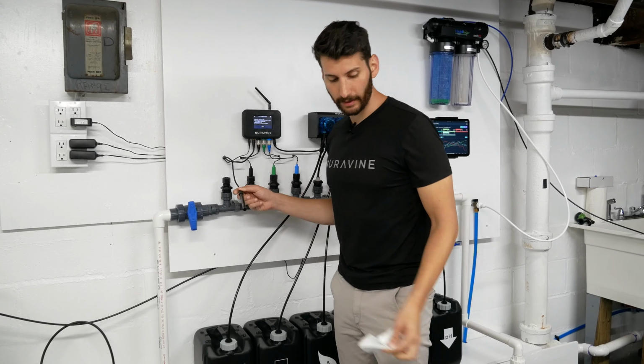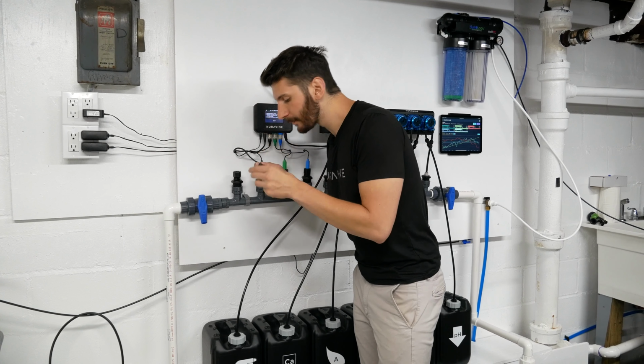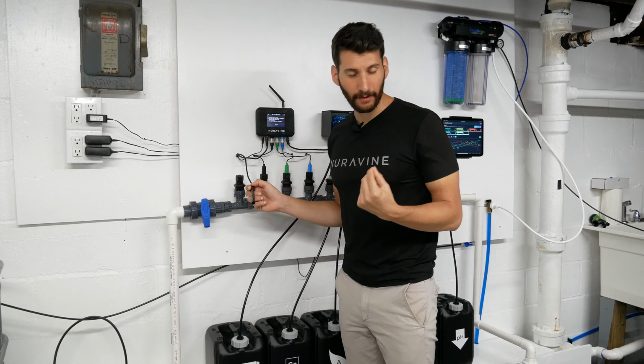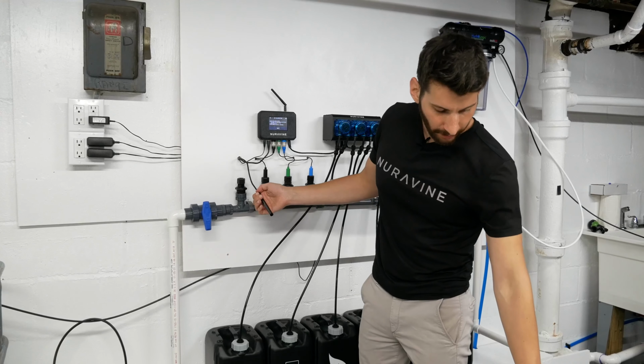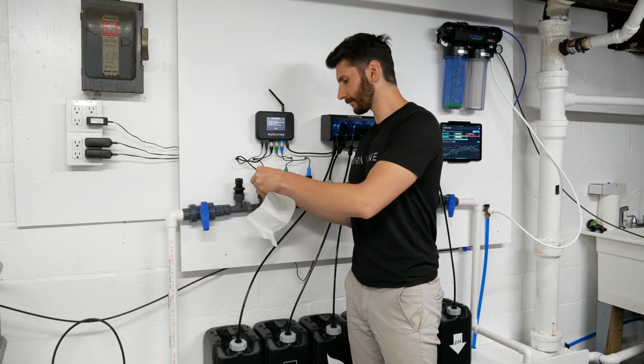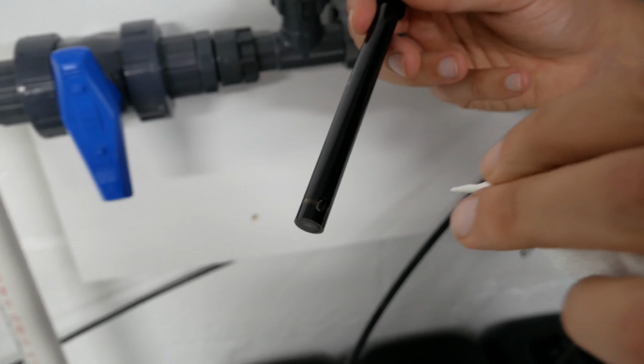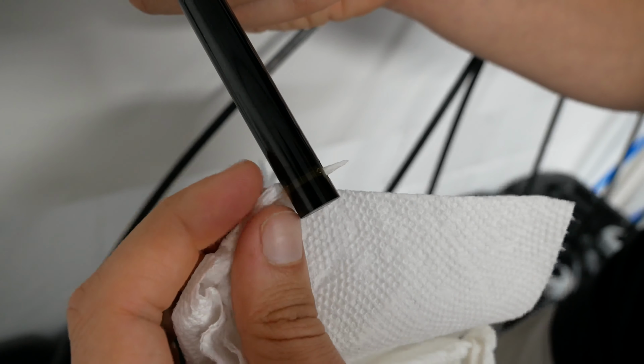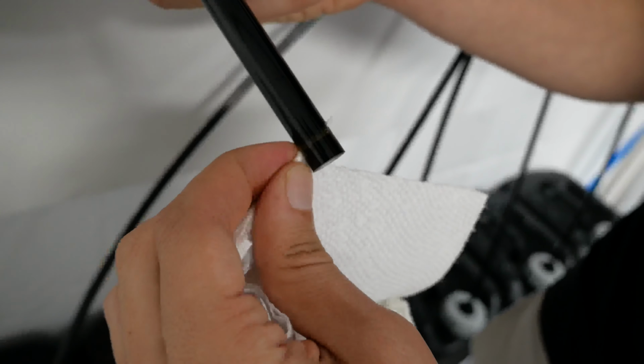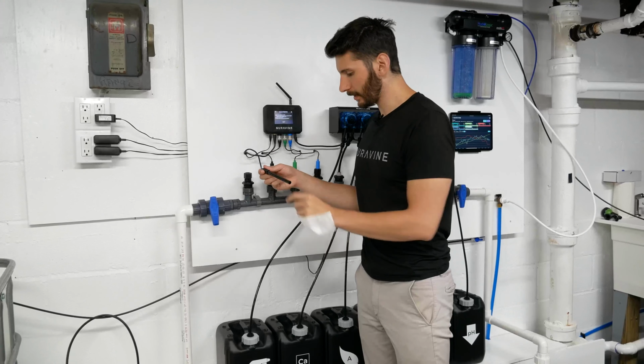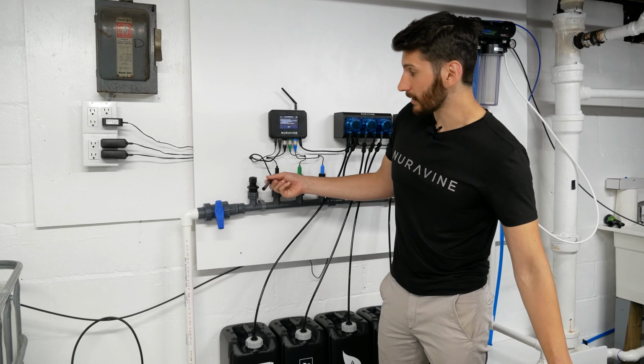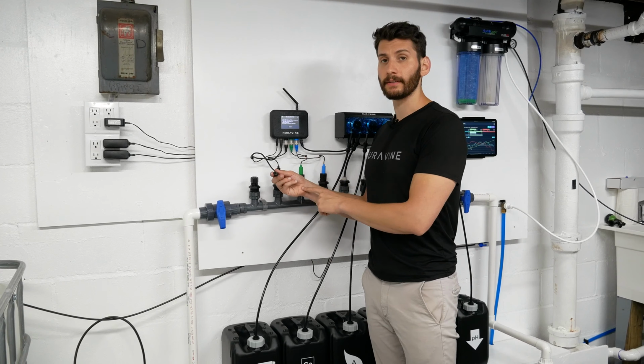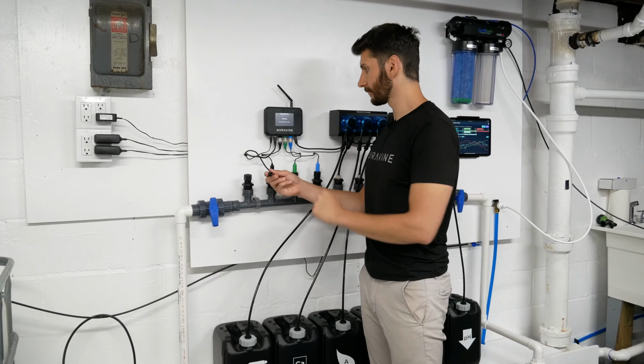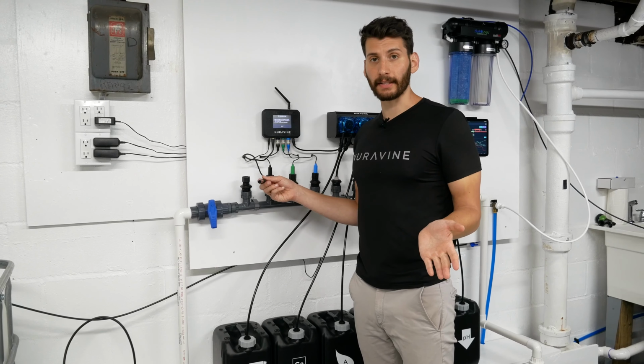Now this is actually super important. There's a hole at the tip that can get water or air stuck in it. So I'm going to give it a little blow. Make sure that there's nothing in there. If you want to be super careful, what you can sometimes do is take your cloth, twist it up at the end like this, and thread it through the hole. All right, so now we've got it as clean as possible, and we're going to perform the air calibration. That only takes a couple of seconds.